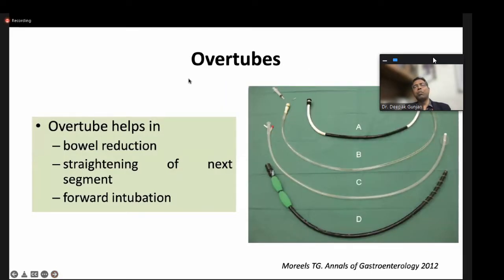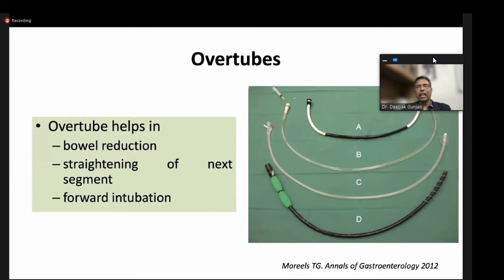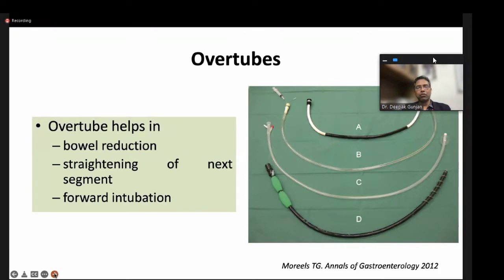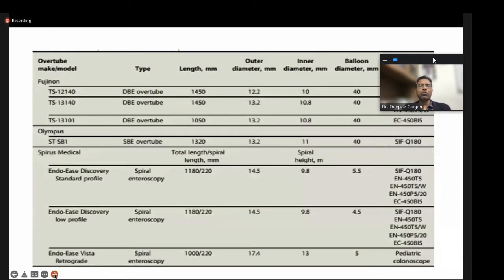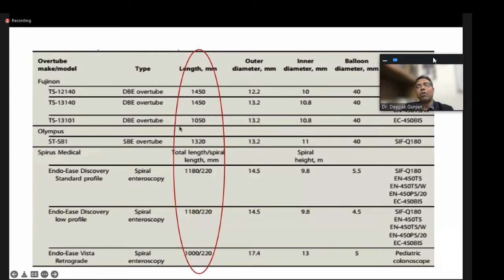The overtubes for spiral, single-balloon, and double-balloon enteroscopes are also very long — more than one meter — which can hinder deep enteroscoping. The double-balloon enteroscope has latex balloons both at the tip of the endoscope and at the tip of the overtube. It cannot be used in patients with latex allergy. It has a balloon pump system that helps in inflating and deflating both the overtube and endoscope balloons, allowing deep advancement.